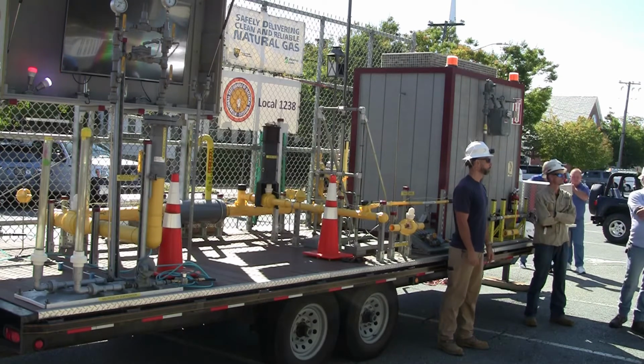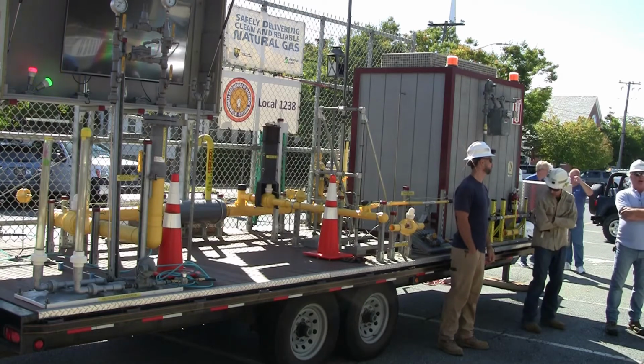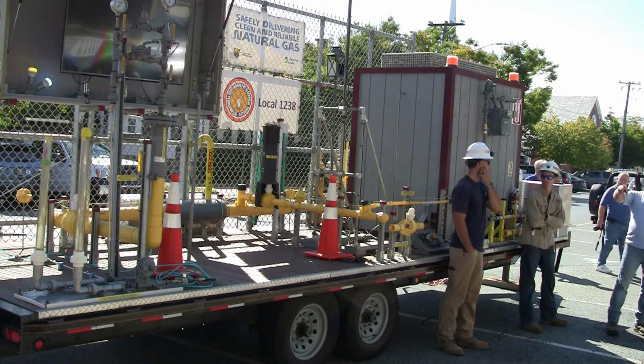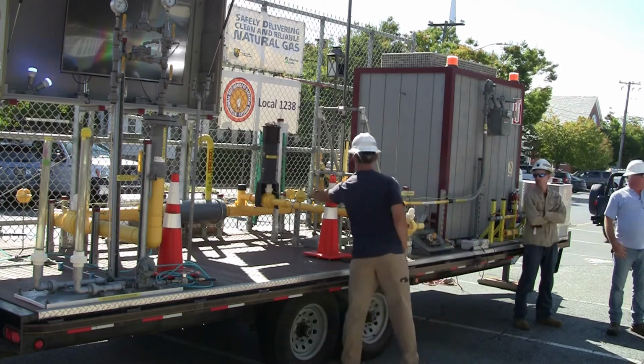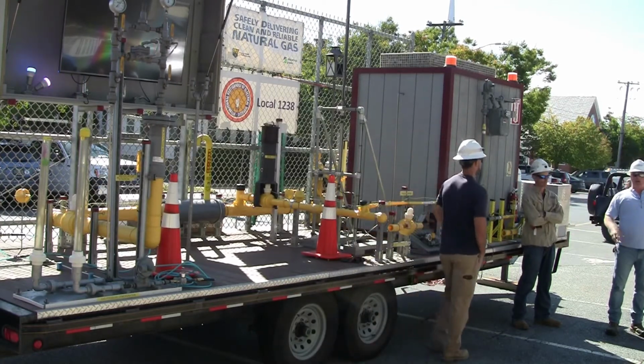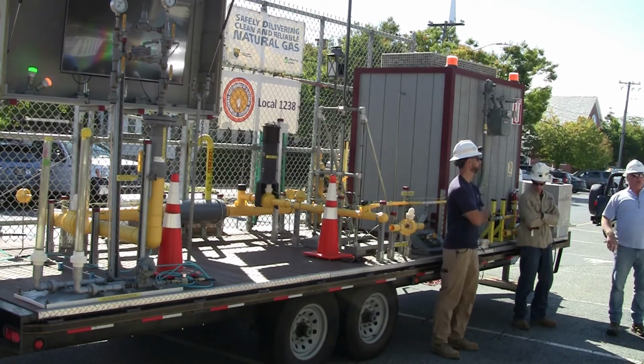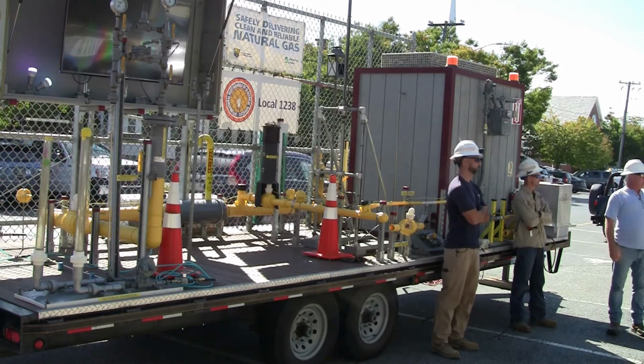We don't have any equipment that can pick up plastic. There's just nothing out there. So that's the reason we run the tracer wire on everything. And you'll see the yellow balls in different locations. Those are called ball markers. We have a special piece of equipment that'll detect those ball markers, and we usually drop those near critical spots, either on a fitting where we're joining pipe together, or a valve that's critical to us, that we lose the box from. Just different types of things that we'll put those on.